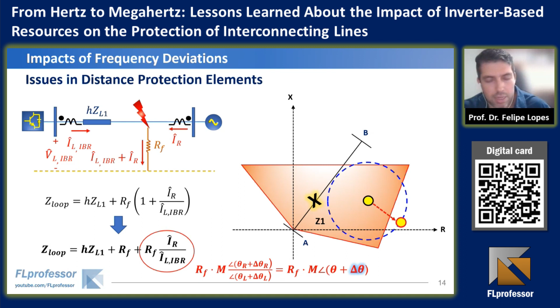and this impedance is supposed to take place here, but it is moved toward the right side and here, and if a rotating characteristic takes place, we start with an underreach problem, and after some time, depending on this rotating characteristic, the impedance will take place inside the operation zone. So we start with an erroneous operation, and then we become a correct operation.